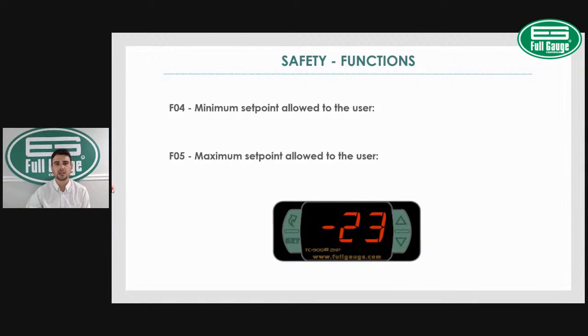So the end users will not be able to go above or below those settings. That's for safety. So if you're setting your system from 32 to 36, you might want to set F04 to 28 or 30 and F05 to 40, 44. So that way, end users will not be able to tamper with the controller outside this range.